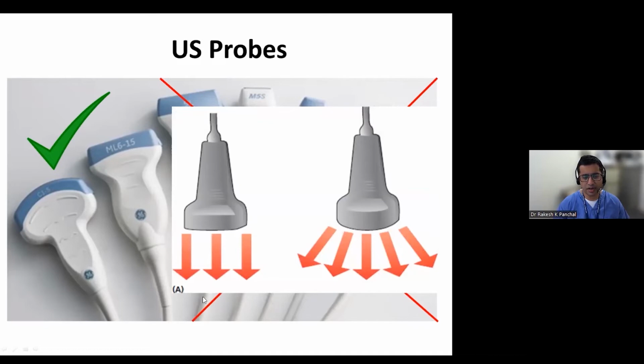So on the left here, you can see the linear ultrasound probe. This gives you high resolution of superficial structures, but not much depth. And a lot of you will be accustomed to using this for vascular access. The curvilinear probe gives you a wider array, superficial detail, but also a lot more depth, and is what we routinely tend to use when we talk about thoracic ultrasound.